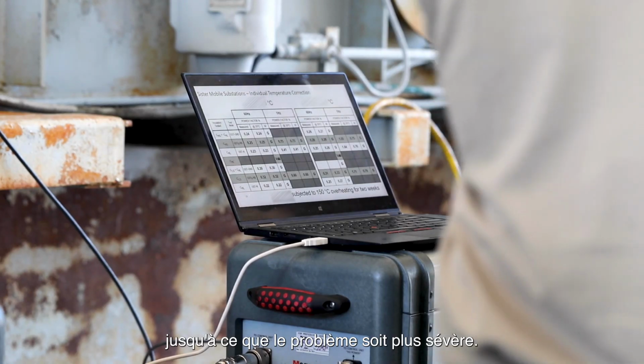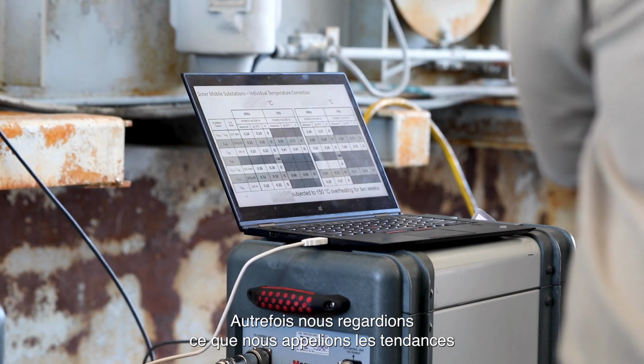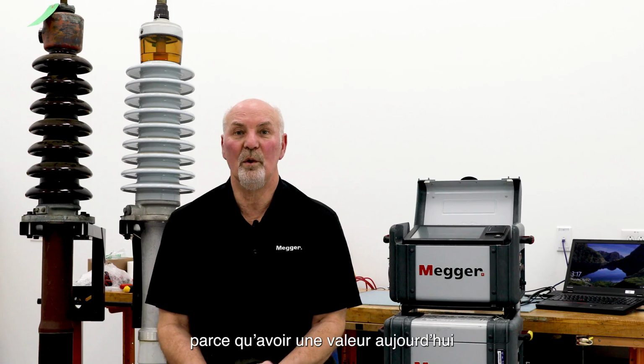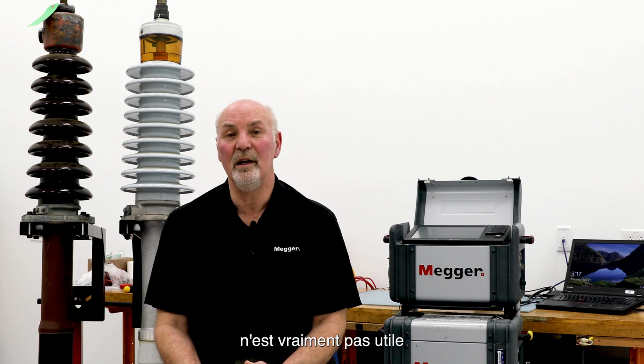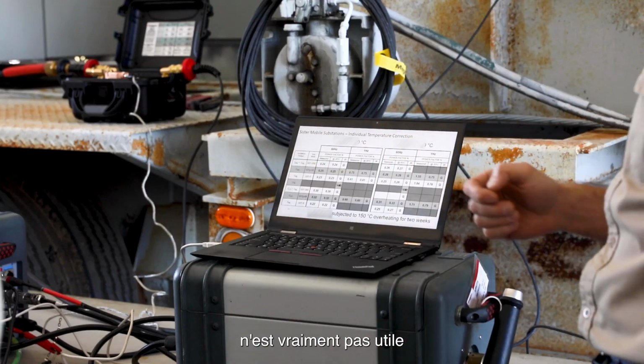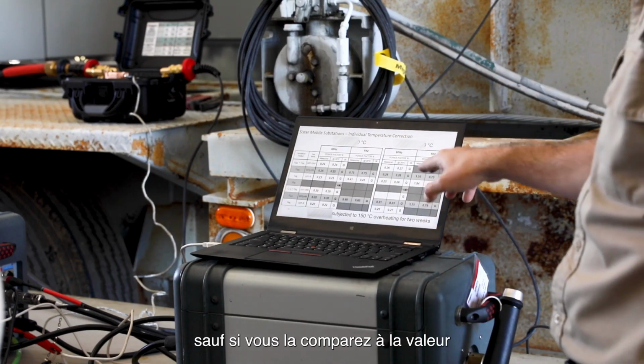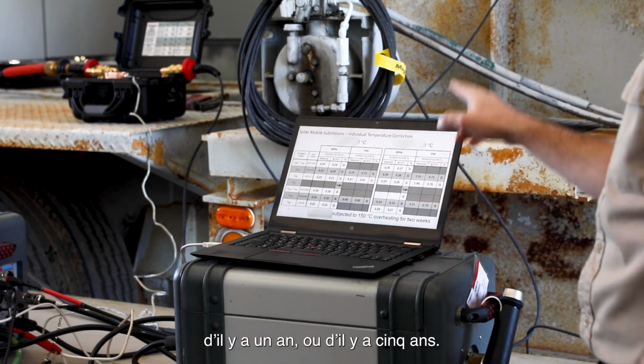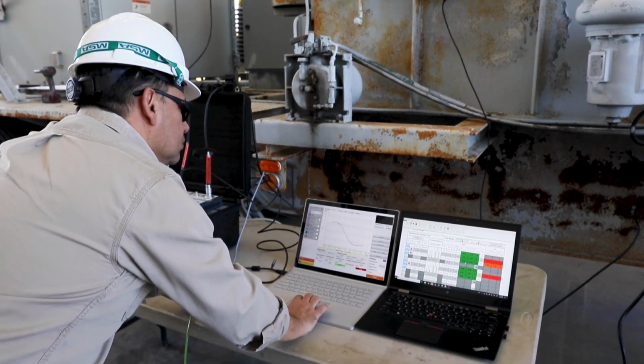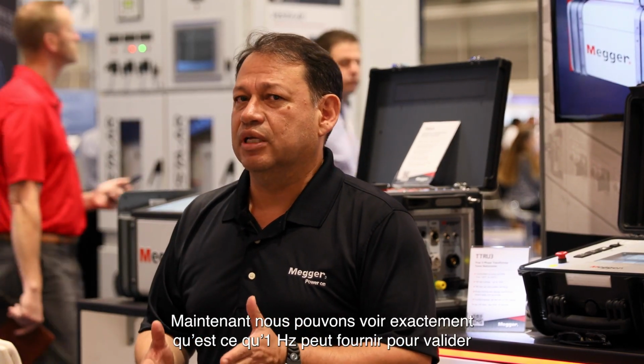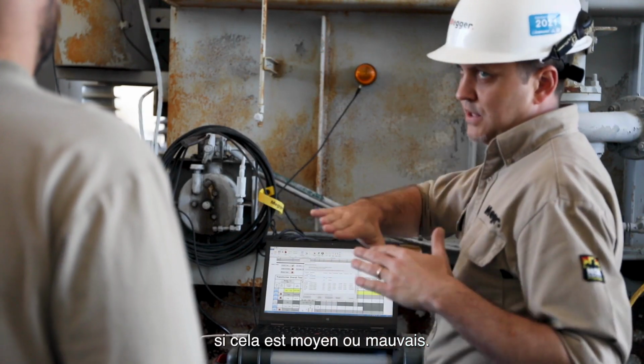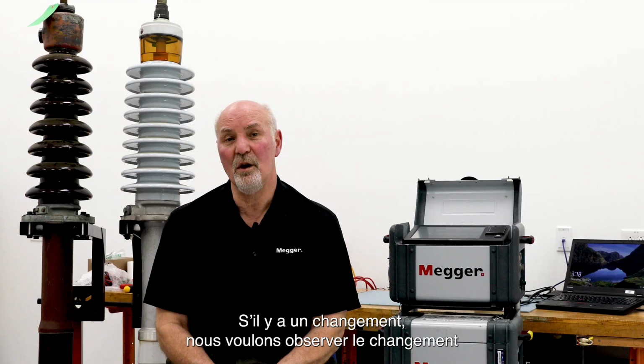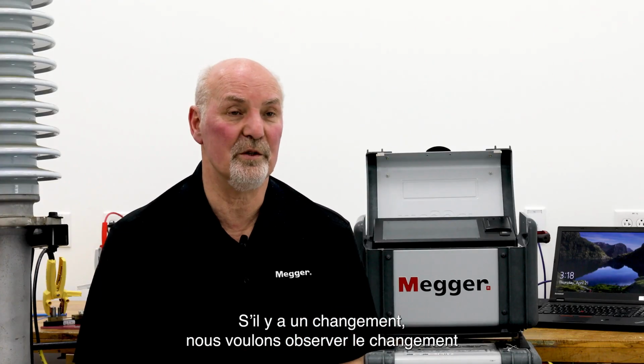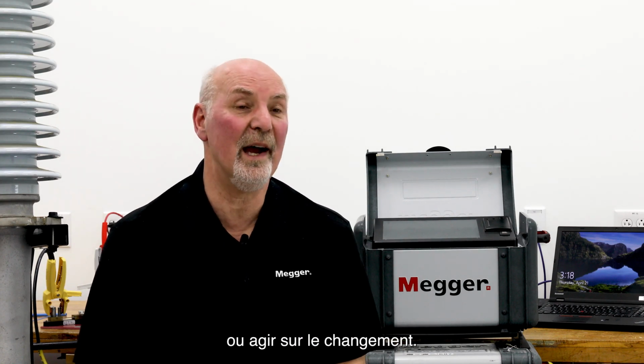In the old days, we looked at something called trending because having a value today was really not of any good unless you could compare it to what the value was a year ago, 5 years ago. Now we're able to see exactly what 1 hertz can provide to validate if a 60 hertz number is good, it's average, or it's bad. If there is change, we want to observe the change or act on the change. So if the change is significant, we need to act on it.